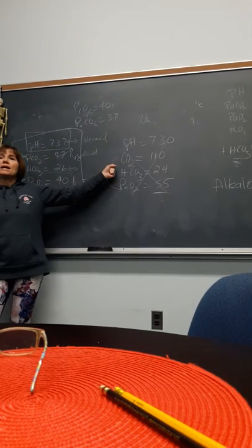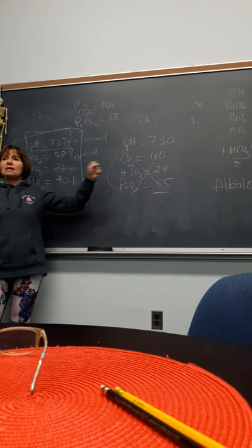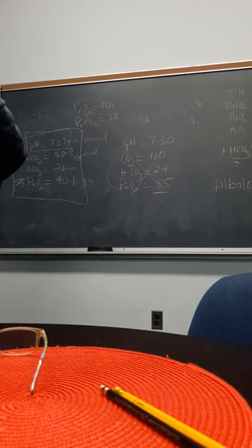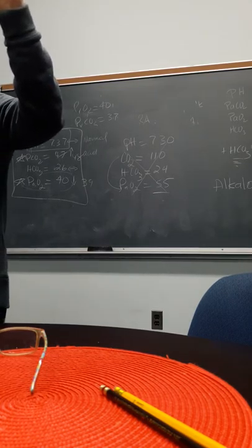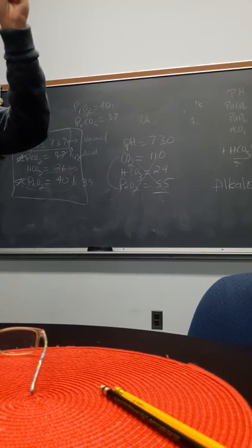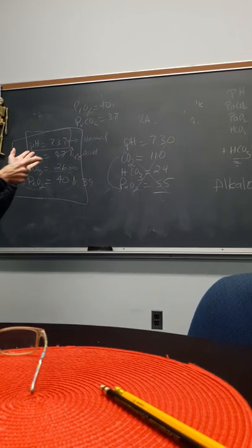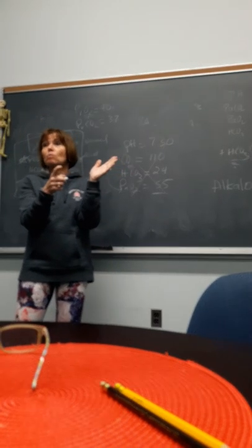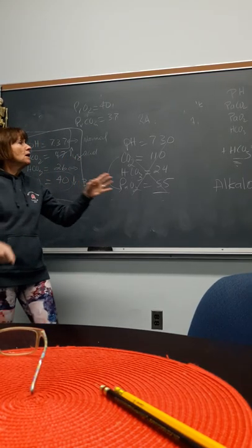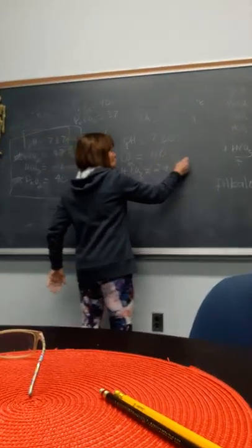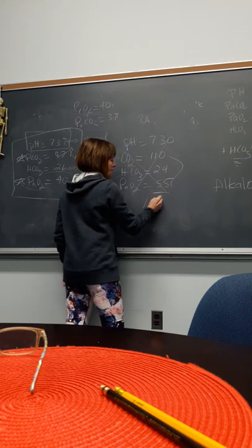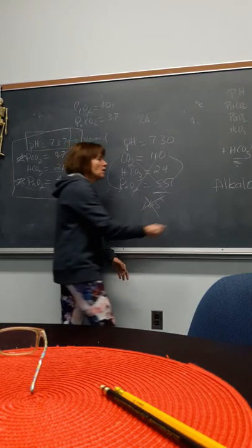Because this didn't, I either have a blood gas machine that's not calibrated correctly, and you need to do QC. Now, I know Melissa did QC with you guys yesterday. What she was doing was putting that vial through to see if it comes in the parameters. If it didn't, then she's going to take the blood gas machine out of service and figure out what the problem is. Okay? So because these two add up to 165, that's physiologically impossible.